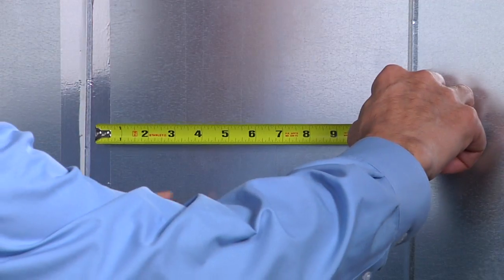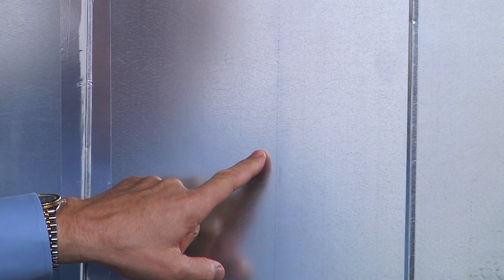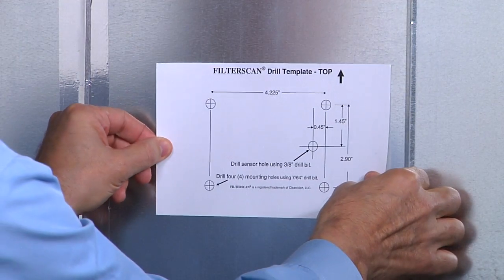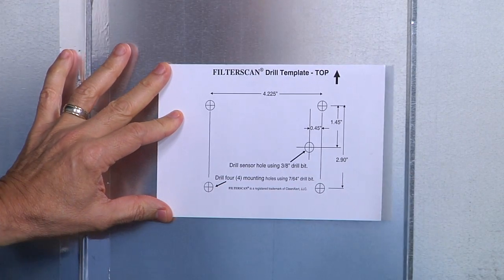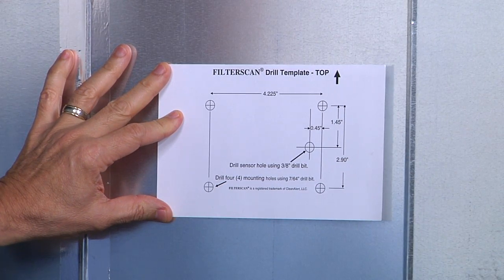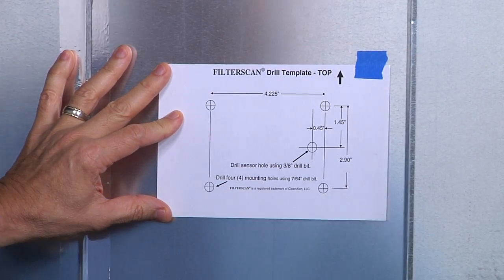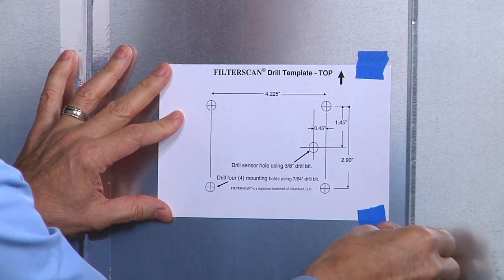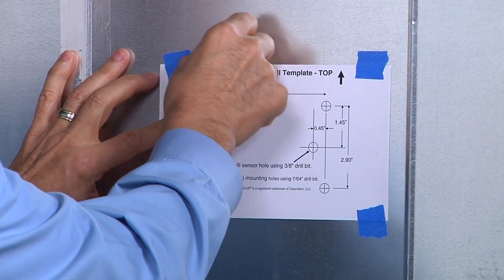Before starting installation, ensure that the HVAC system blower, motor, and fan is turned off and remains off until told otherwise. The Filterscan monitor is attached to the external wall of the air duct, either upstream or downstream from the filter to be monitored. The minimum distance for positioning the monitor from the air filter is 6 inches. Locate an area on the return duct from the air filter large enough to place the monitor template on a flat surface and where there are no obstacles inside the duct. There should be sufficient clearance from the surrounding walls and from any components of the air supply system to easily access the monitor after installation.